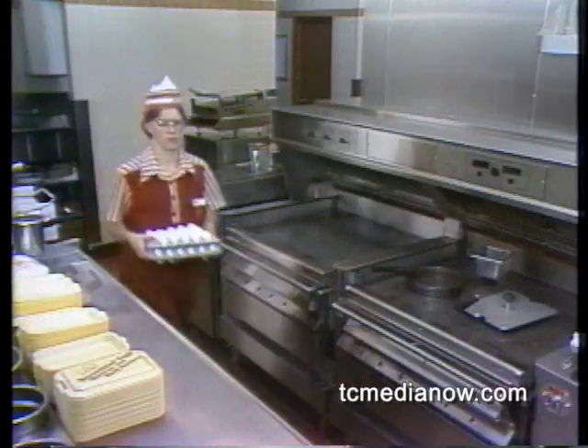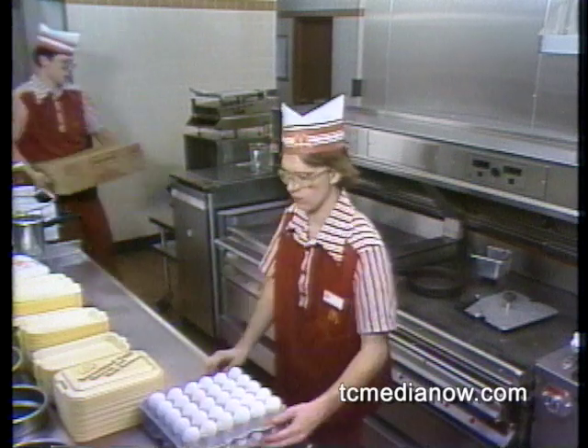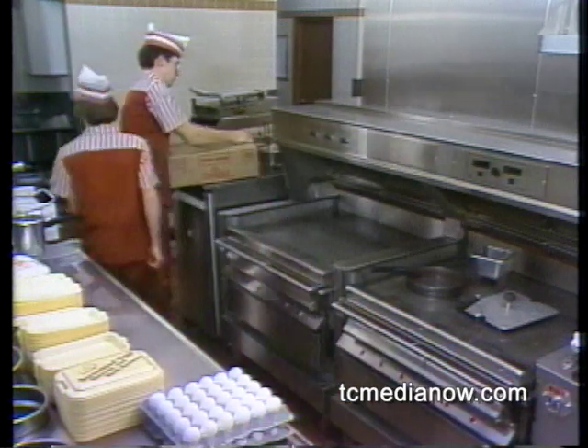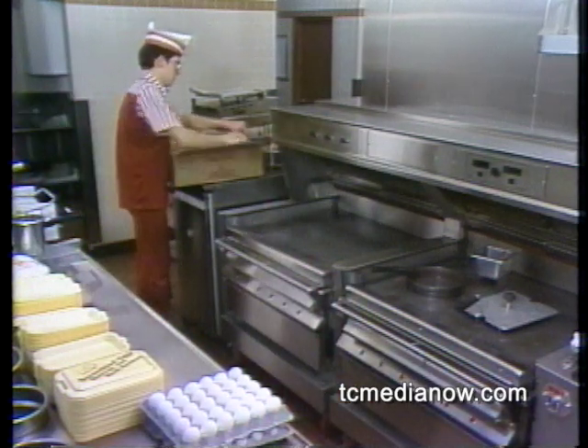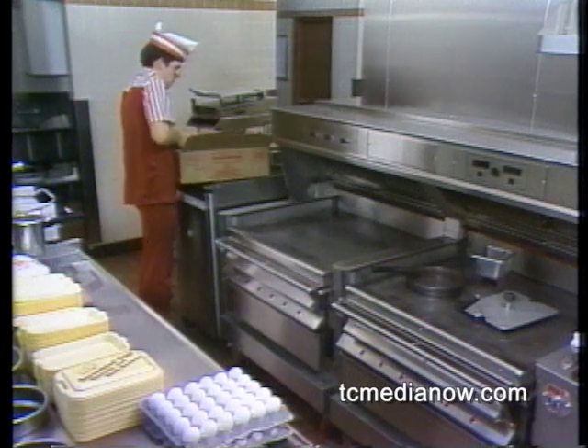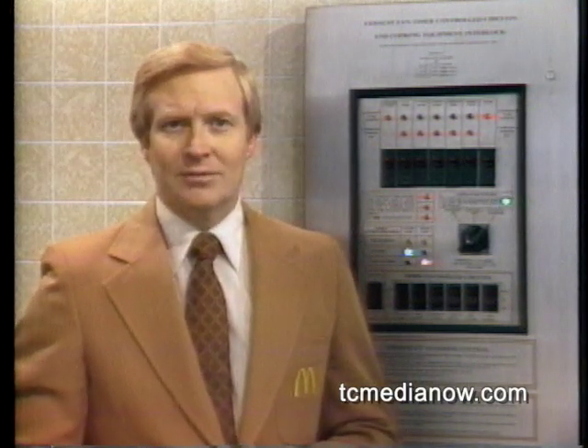The button lights when it's pushed, and now all the kitchen HVAC equipment is fully operational, and power is supplied to all the kitchen equipment as well. Use an up-to-date equipment schedule to determine when individual kitchen equipment units should be turned on or off. The energy interlock system does not automate fire-up of kitchen equipment. It simply prevents units from being left on during non-business hours.